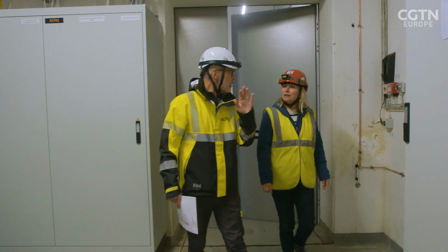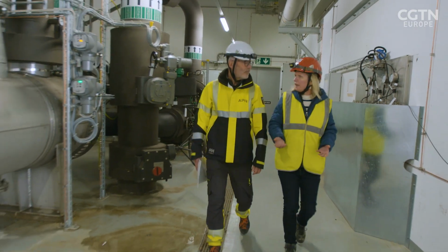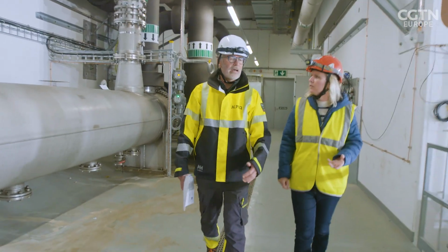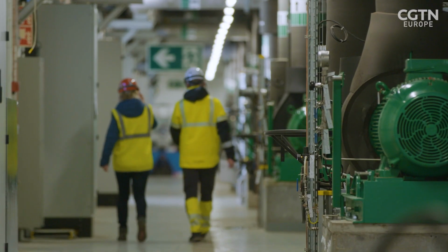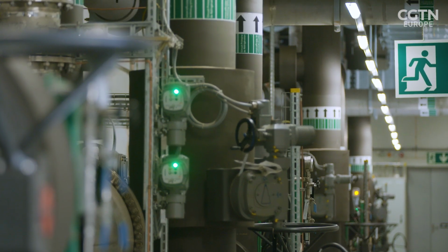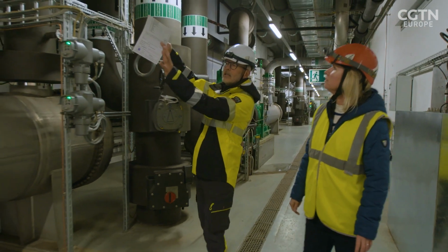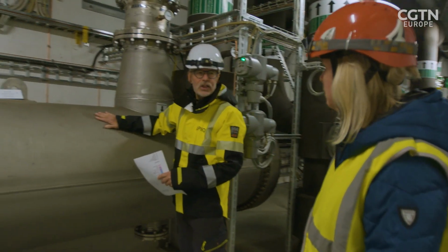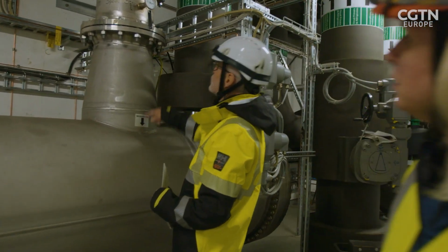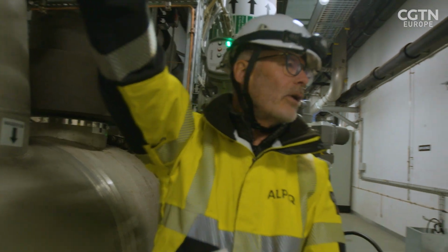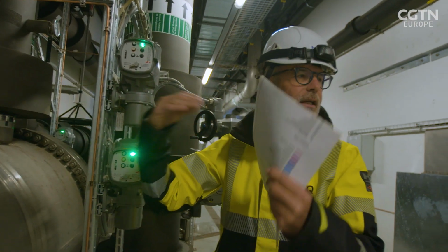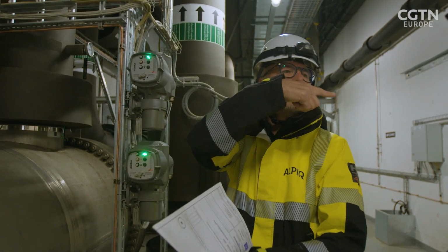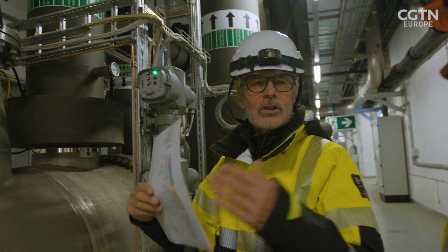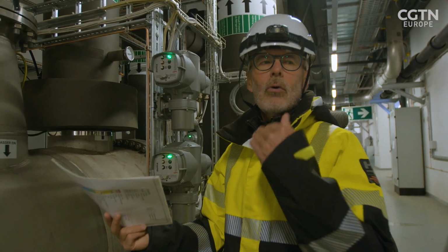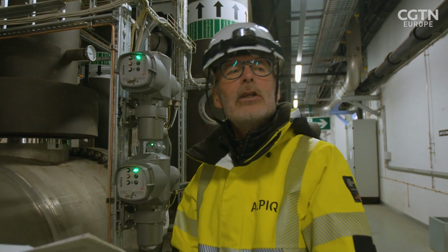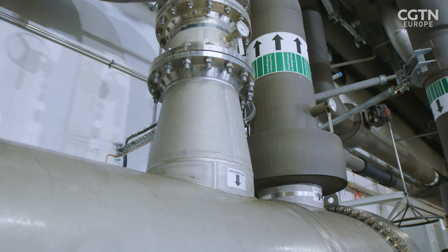So now we are at the very bottom part of the cavern. Wow, it's a lot colder down here. Yeah, it's a bit chilly because we're at the refrigeration level. That's where we have all the cooling systems to cool the machines. So all these pipes are for cooling. If you look here, that's one of the examples. That's a heat exchanger. Here we are getting water inside the heat exchanger. It's going out on the other side, and then you have a secondary loop. This loop is then sending the water through the generator. Because the generator does not have 100% efficiency, part of the energy is transformed into heat, and you need to evacuate this heat. That's the purpose of the cooling system.